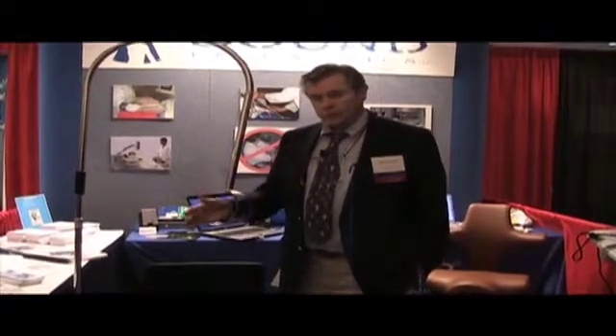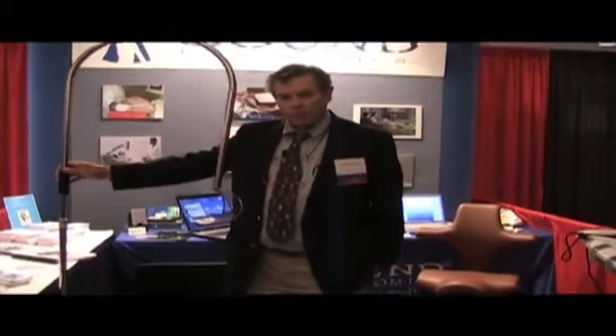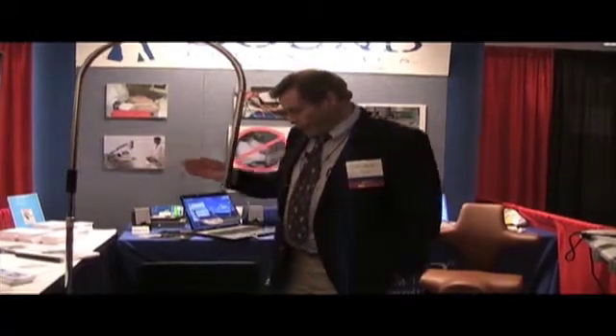This device is called the shoulder assist. When a technician or technologist sets this up adjacent to the patient on the bed, the x-ray table, or the sonographic table, all she has to do is drop her arm into the sling.